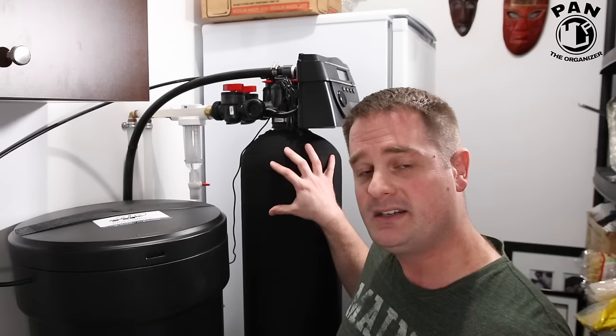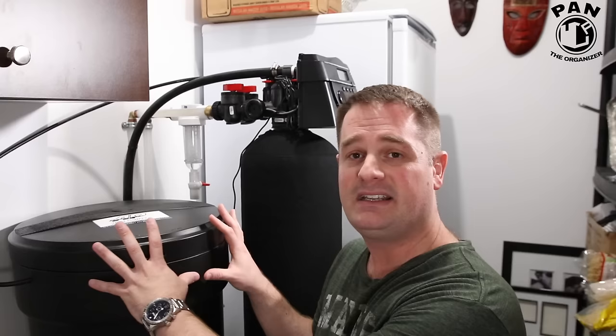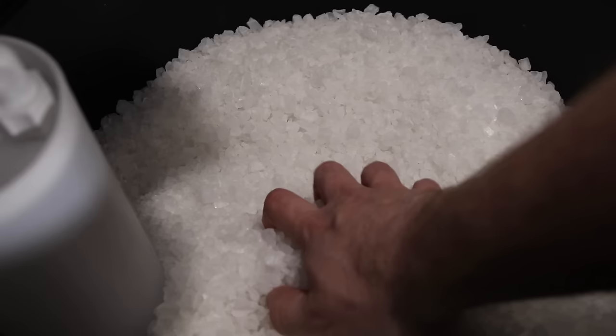A water softener system contains two tanks. The main tank, in which we have the resin that cleans away the water and makes it soft. And then we have a second tank that contains salt. If we open the second tank, you can see there are some fine particles of salt in there, some typical salt. At the bottom of this salt tank, there's also some water in order to create a salt brine.